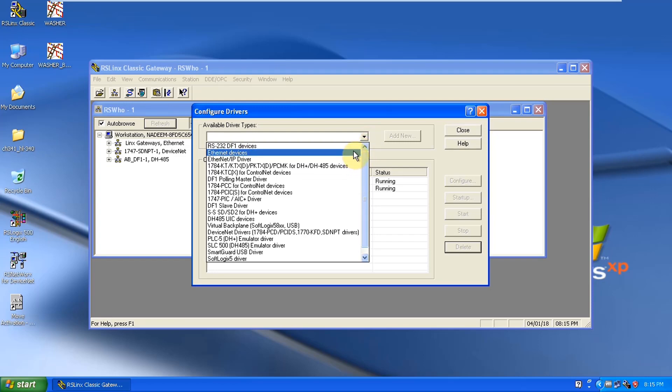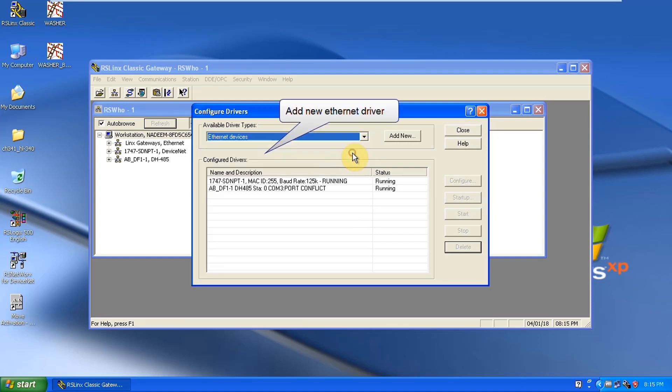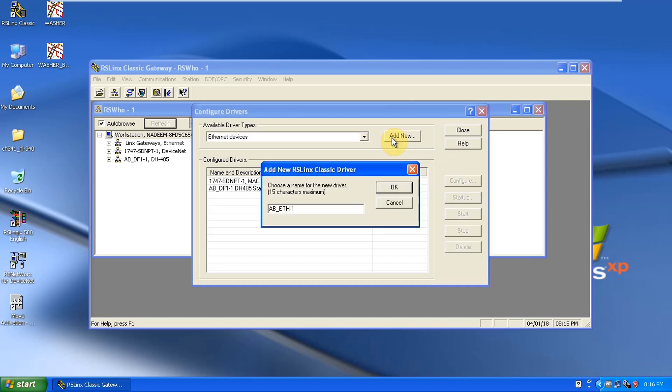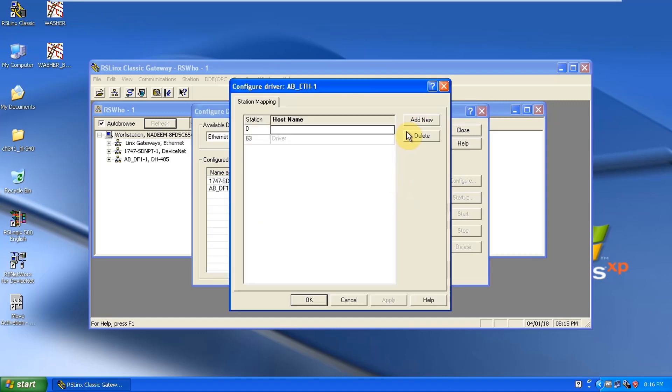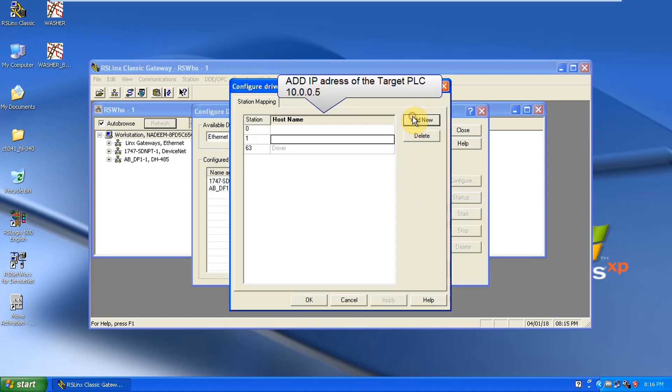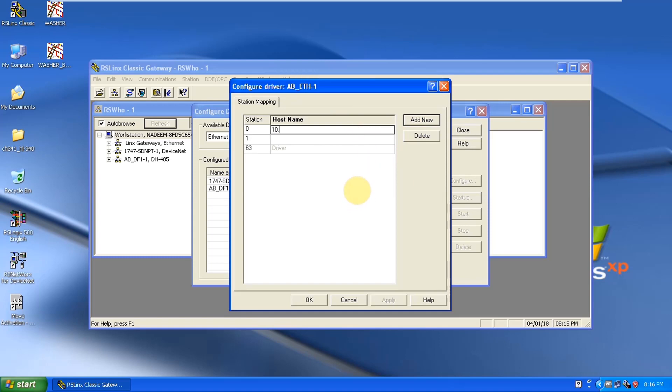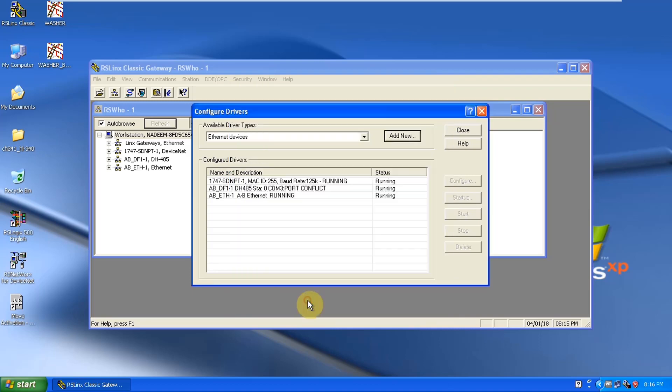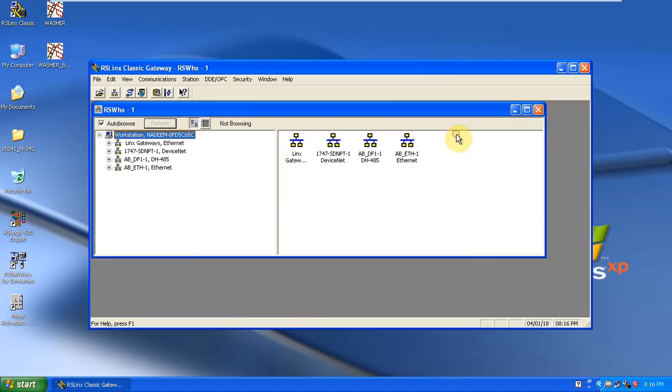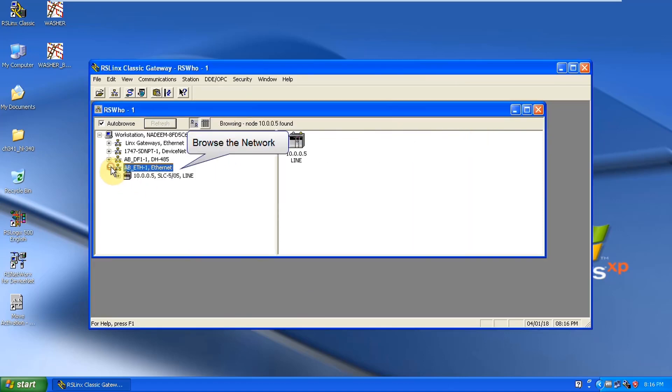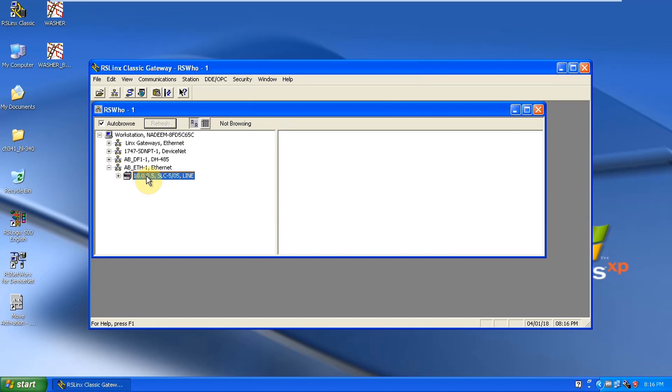Click on browse and then configure drivers, refresh it out if possible and then select Ethernet devices because our PLC is on Ethernet protocol. So we will just define a new PLC, add new. Here you have to define the IP address of a PLC which is 10.0.0.5, close it out.